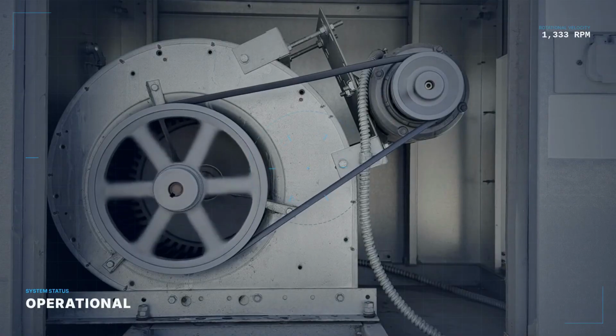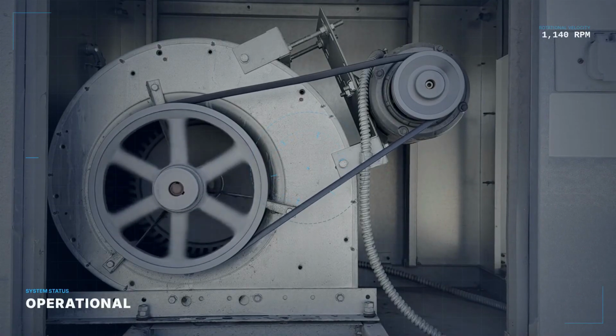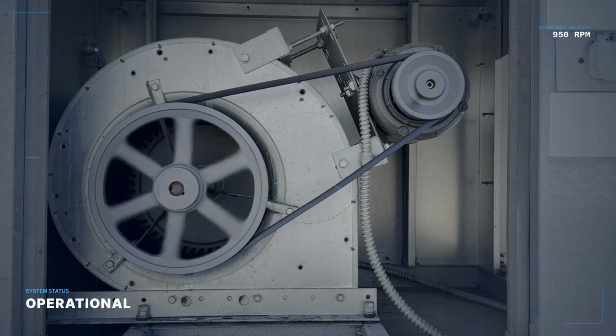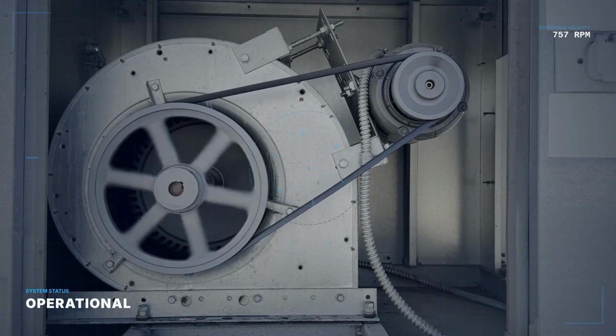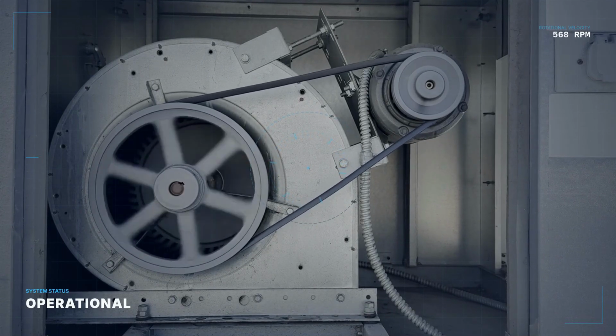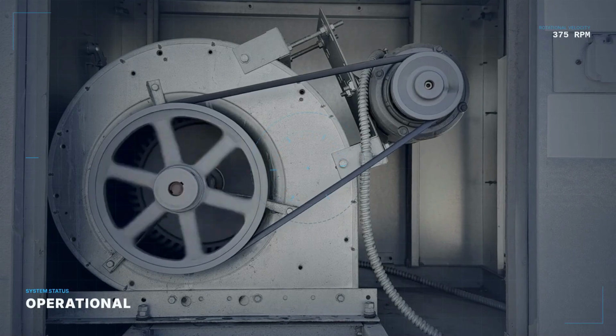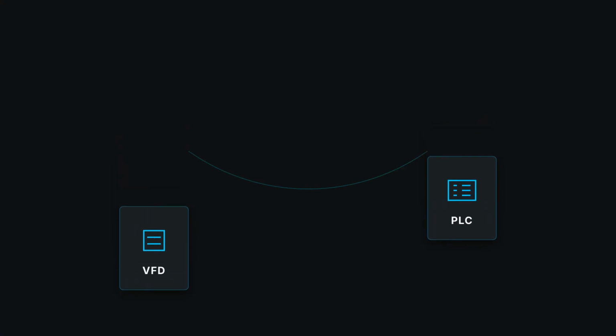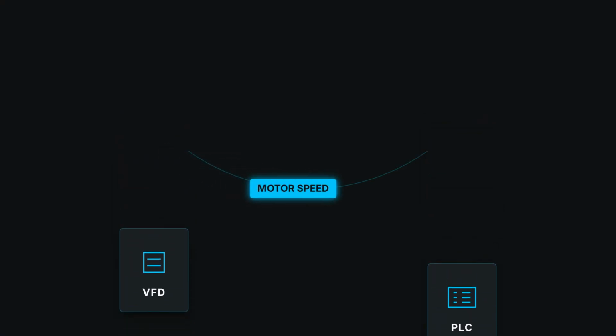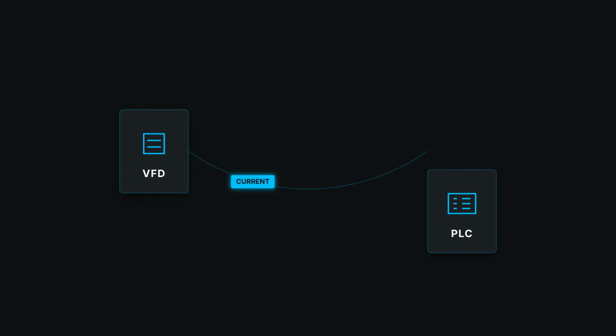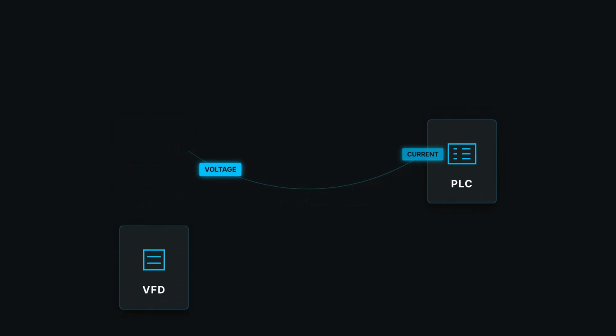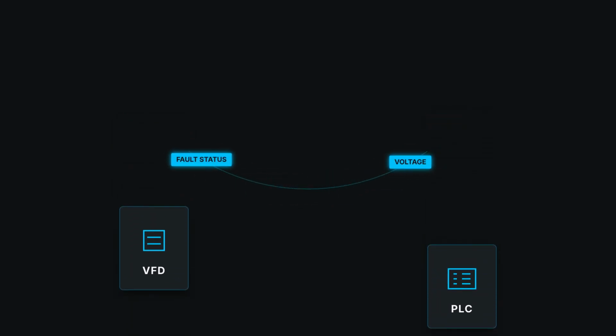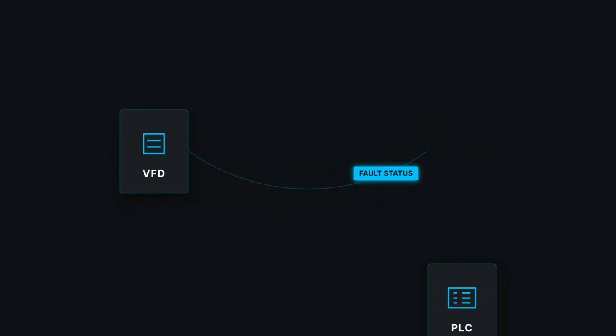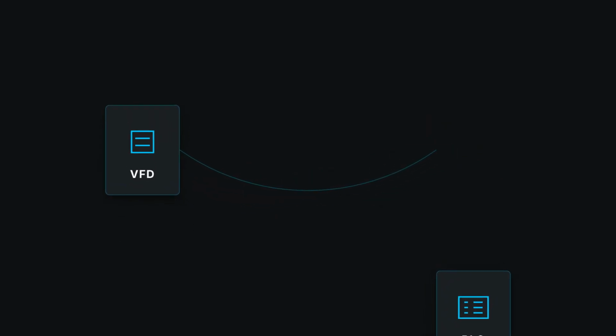Next comes the VFD, variable frequency drive. The PLC and VFD communicate continuously. Suppose a conveyor motor needs to run at different speeds. The PLC sends speed commands to the VFD. The VFD adjusts the motor speed accordingly. At the same time, the VFD sends feedback information back to the PLC, such as motor speed, current, voltage, and fault status. This allows the PLC to monitor and control the motor intelligently.